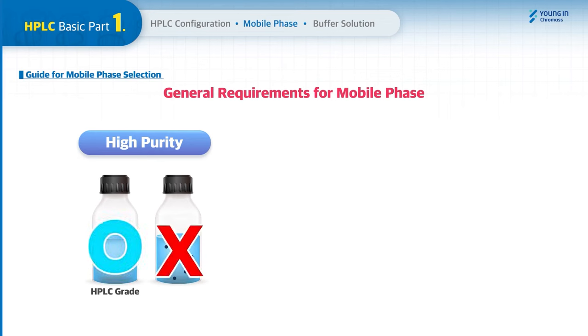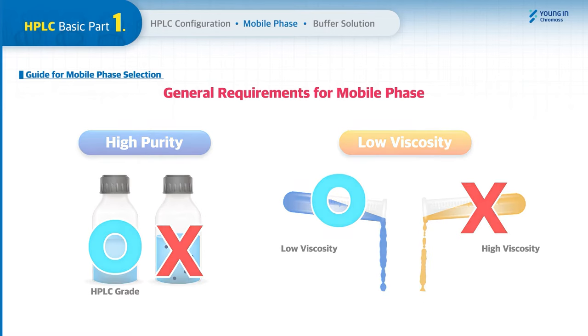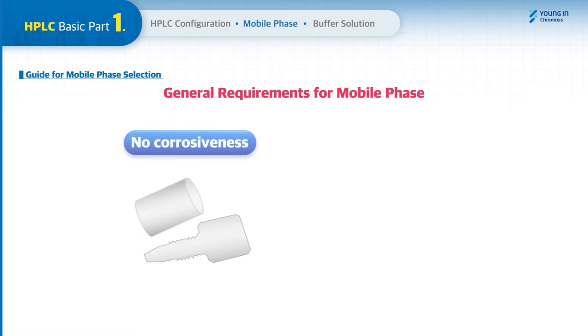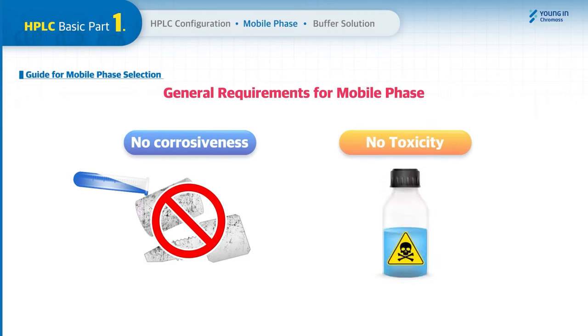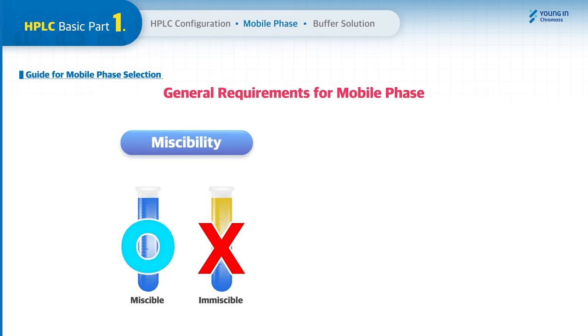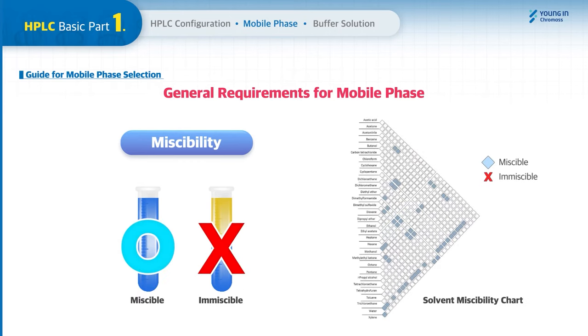There are general requirements for mobile phase that can affect selectivity. First, purity — all solvents should be HPLC grade to have minimal UV absorbance. Mobile phase viscosity should be as low as possible. Solvents must be non-corrosive to HPLC system components and must be considered with respect to health and safety risks. Solvents should be completely miscible with each other in all proportions.